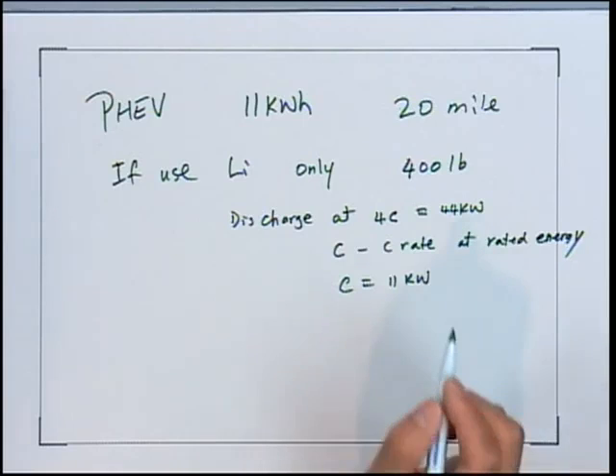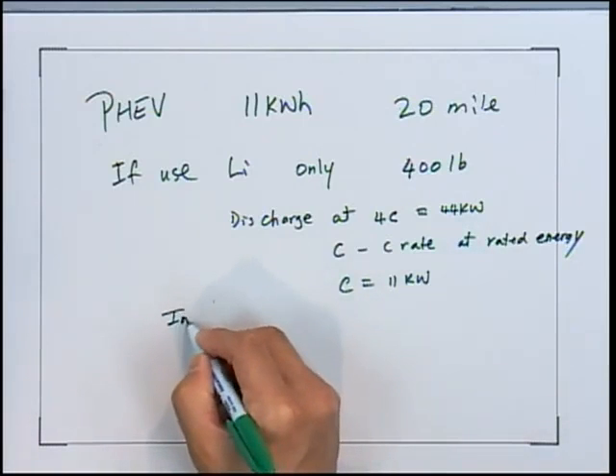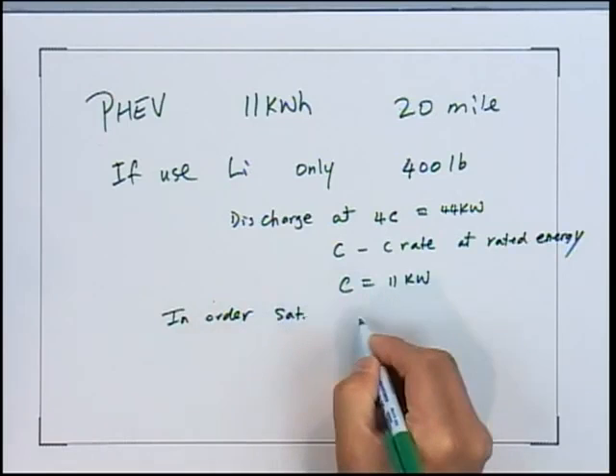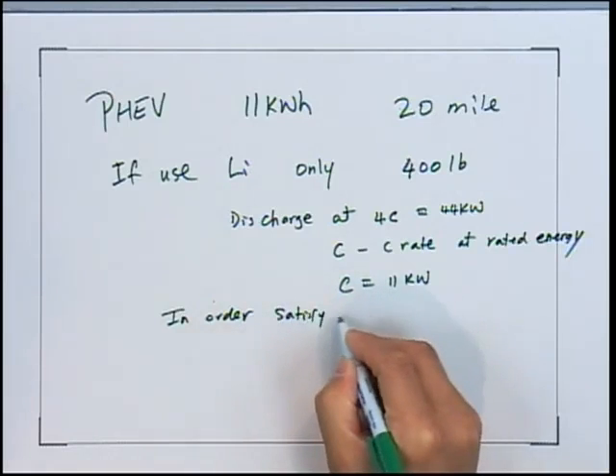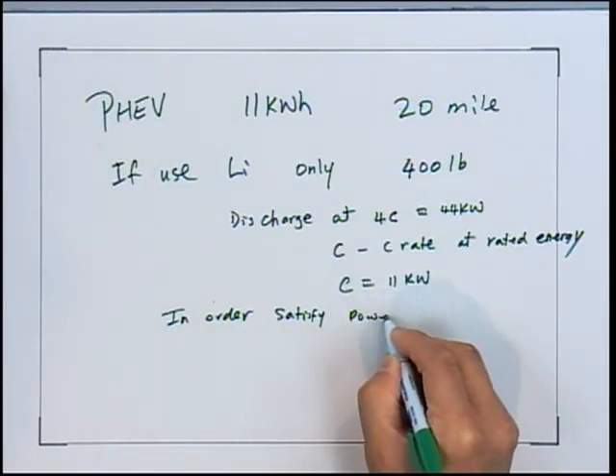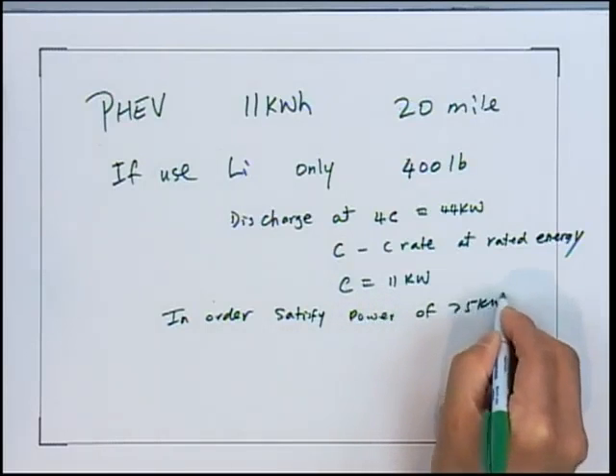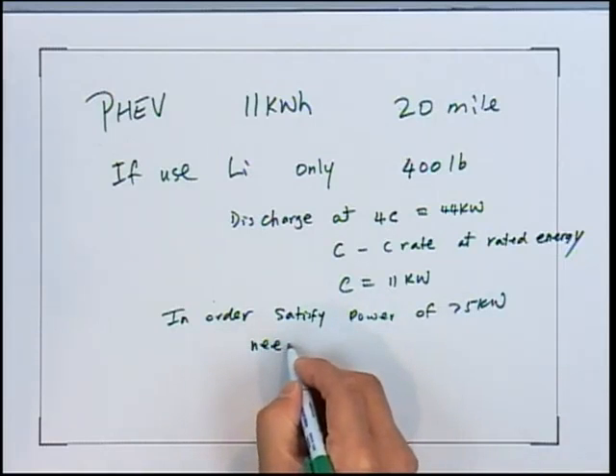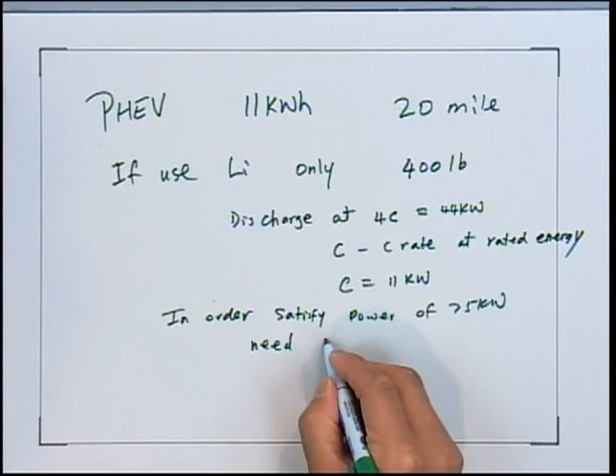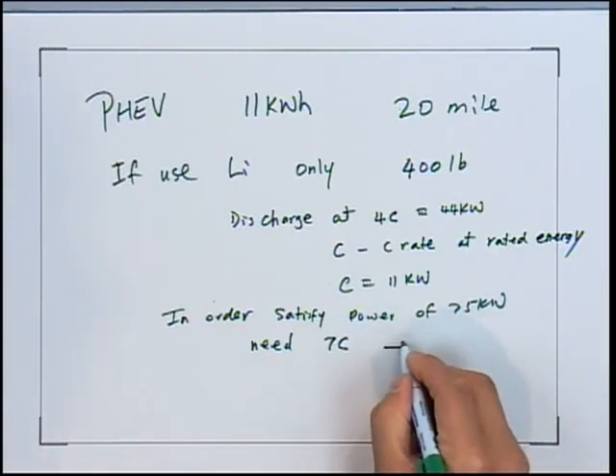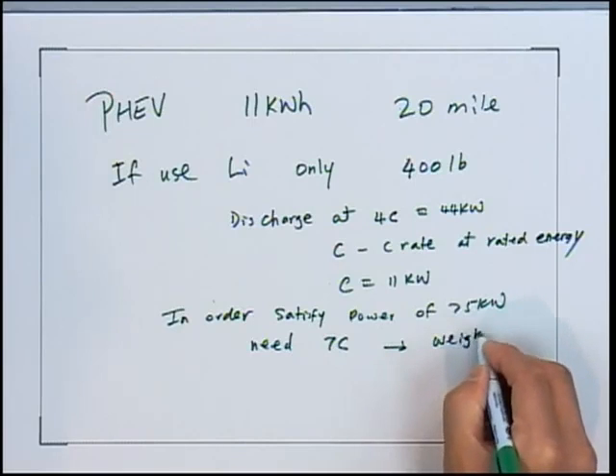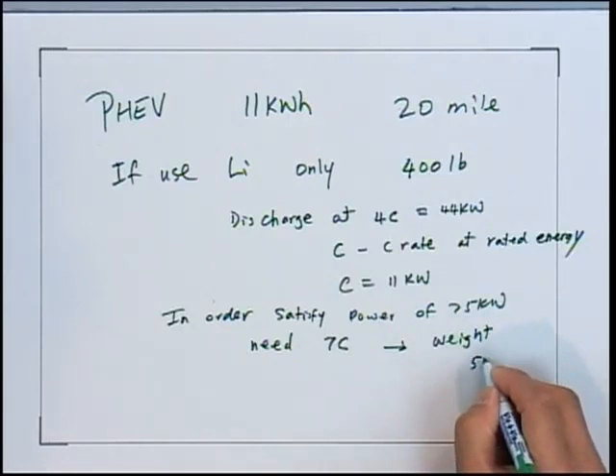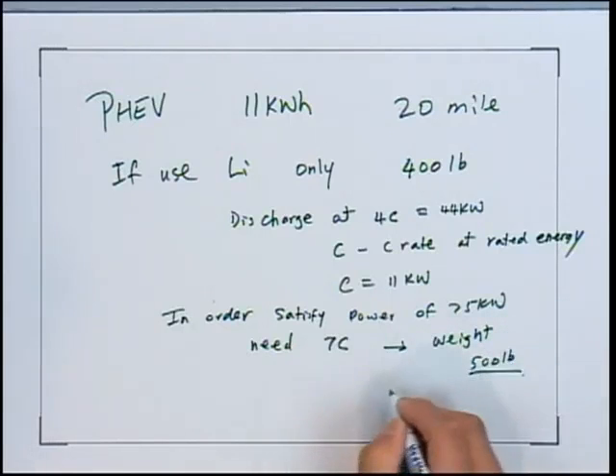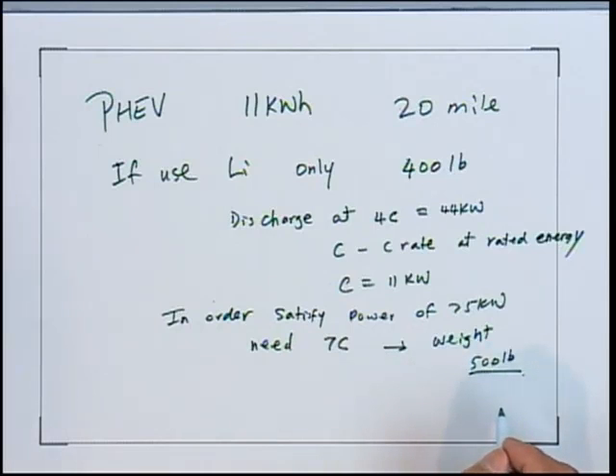So in order to satisfy a power of 70 kilowatts, you need 6C, or actually rather 7C. Therefore, if you have to select a different battery, not the one that we just talked about, you have to select a weight of roughly 500 pounds. Or you have to reduce the energy from 11 maybe to 9. So that's the lithium-ion battery.